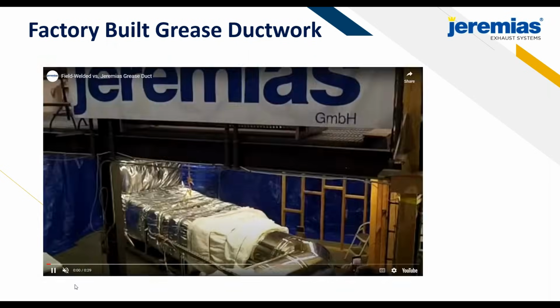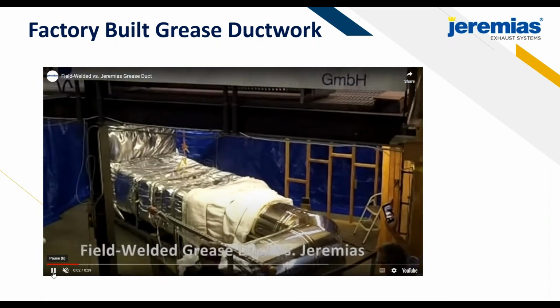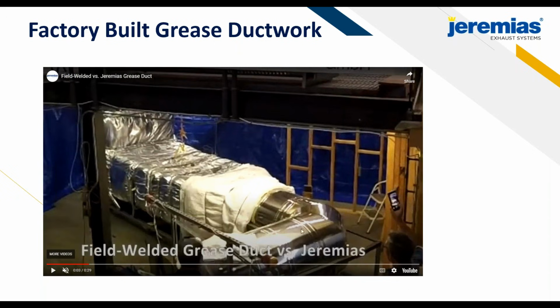I'm going to keep it on mute, but this is a 30-minute 2,000-degree test that they do at the factory. So, factory-built grease duct is required to do this test. It's a 30-minute 2,000-degree test. And what they did on this one, they decided to build their own field welded test to just demonstrate the differences in quality that you get with the factory-built UL listed product versus something that's built and welded in the field.